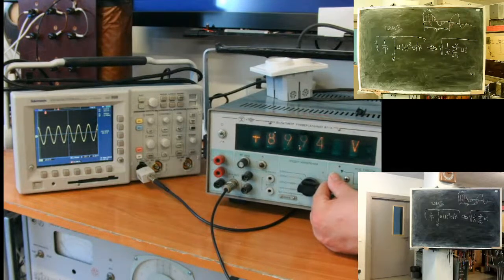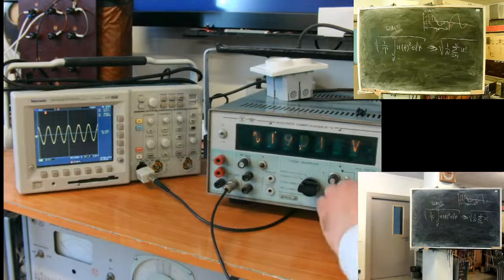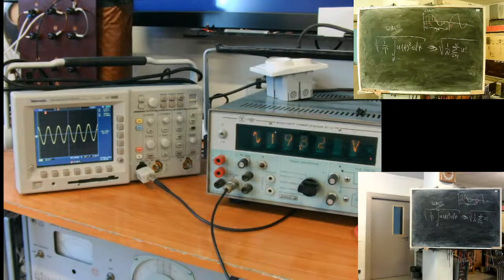Calibration, 8980, I should say. Zero, 19.82 instead of 20. We got what we got. If I add some third harmonic, should be 24.4, we have 17.8. And you can see 22, 23. Should be 22.9, okay.